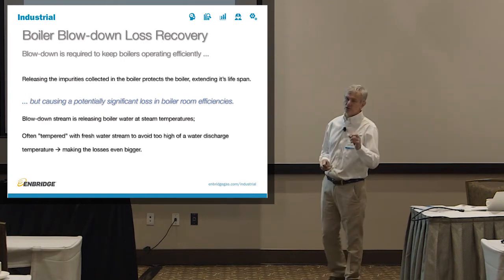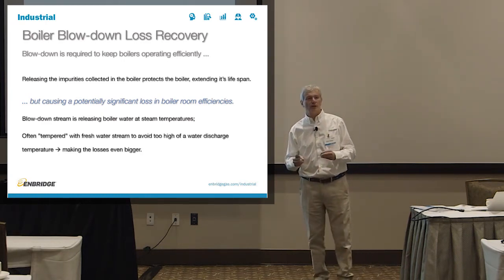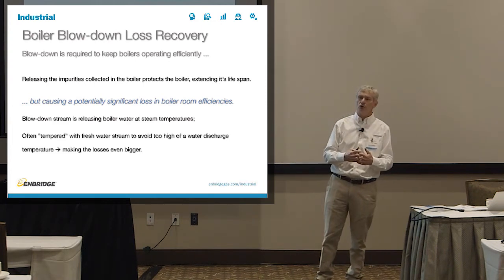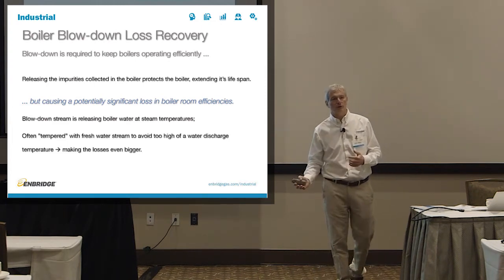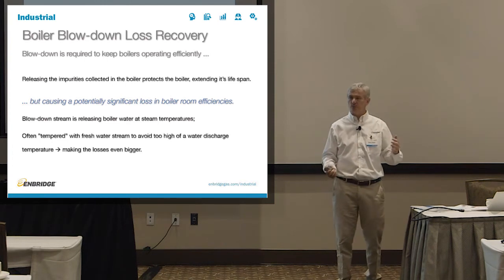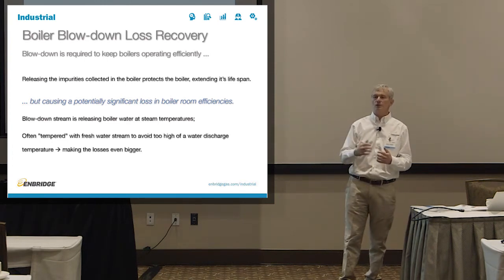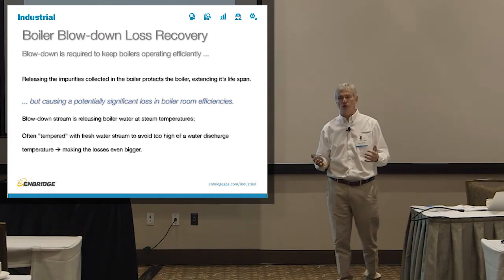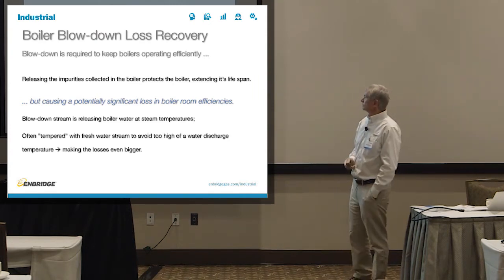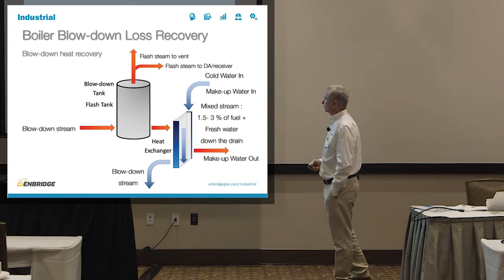Worst part is, because it's so hot, usually you have to mix it with cold water to actually be allowed to put it into your sewer. So you're not only losing the energy from the boiler, you're also losing the cold water that you put in. And as we all know, water is not cheap. So how does it work essentially?